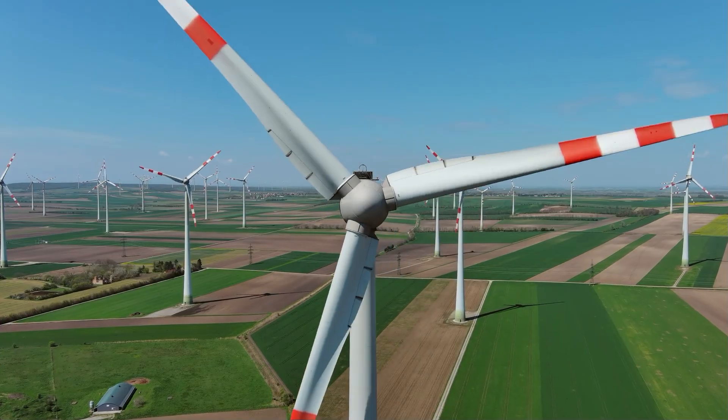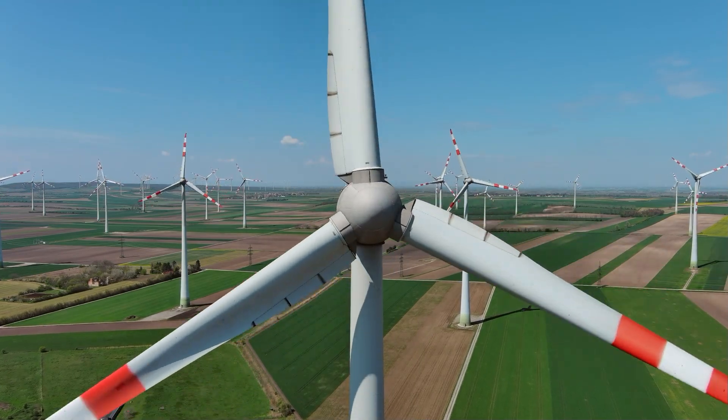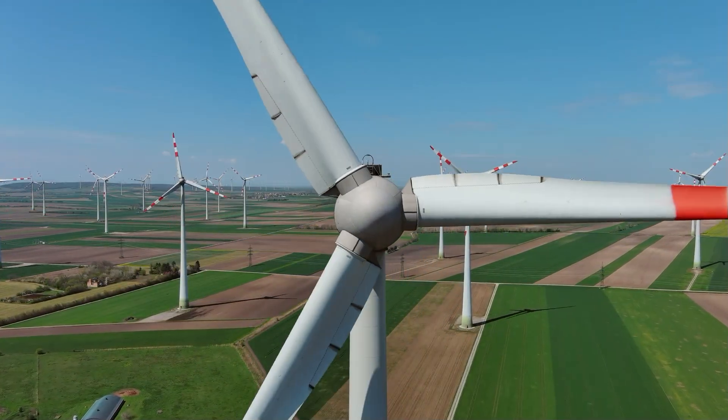So that's a traditional power grid. But why is inertia a problem with green energy? Green energy power generation in and of itself has zero inertia. What about wind turbines? Many wind turbines don't even generate AC directly — they generate DC and that power is fed through an inverter. In any case, you can't make the wind blow more, so even wind power has almost zero inertia.